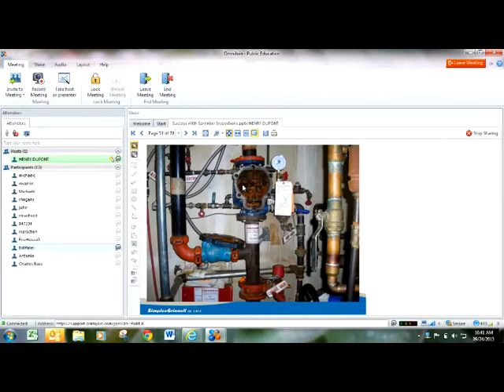where you can put it in your system and it kills that bacteria. So we would go in and flush the system free of all of the obstructing material, and then we would install that Pipe Shield system to mitigate any future microbiologically influenced corrosion.